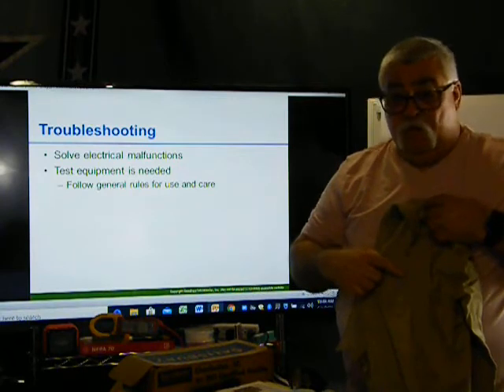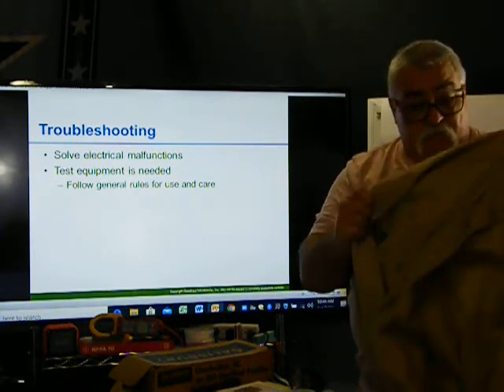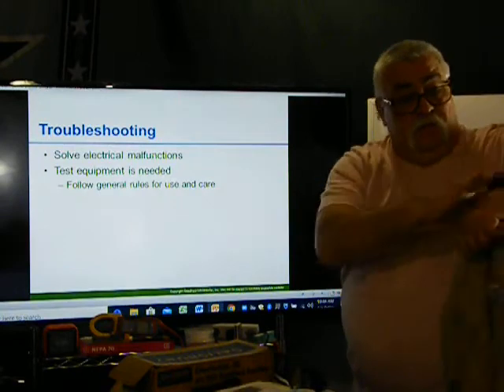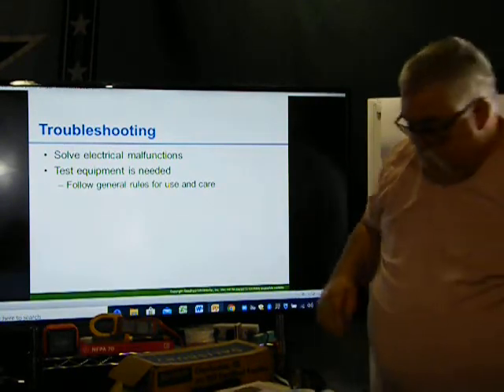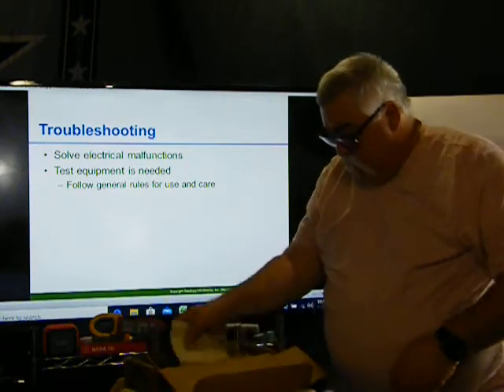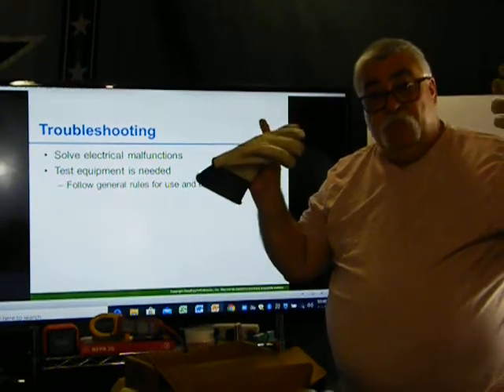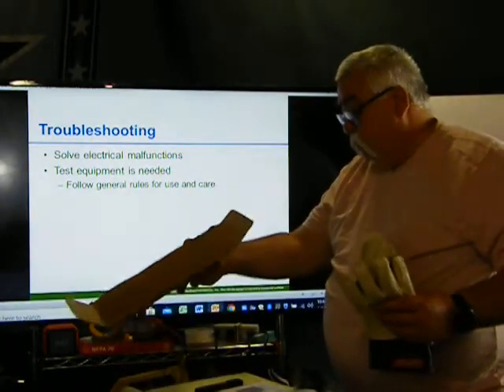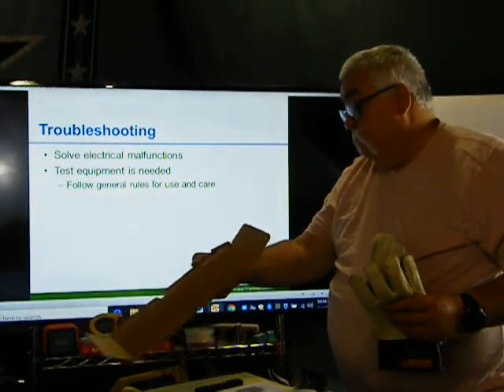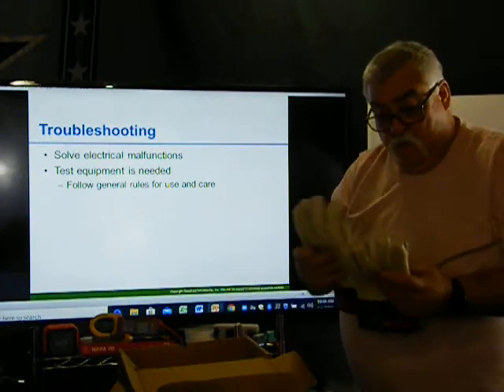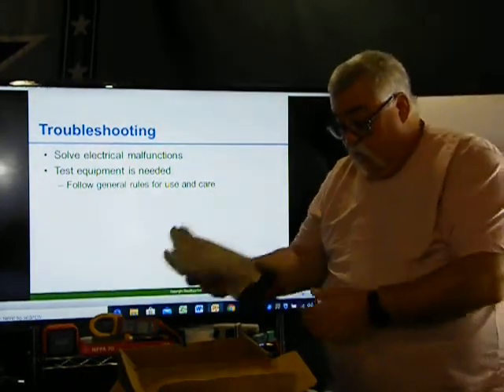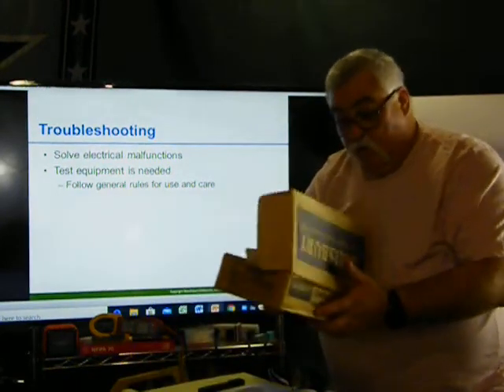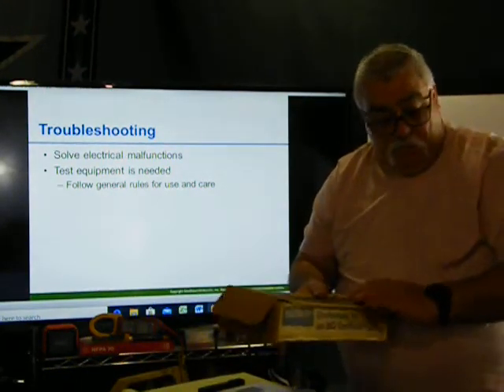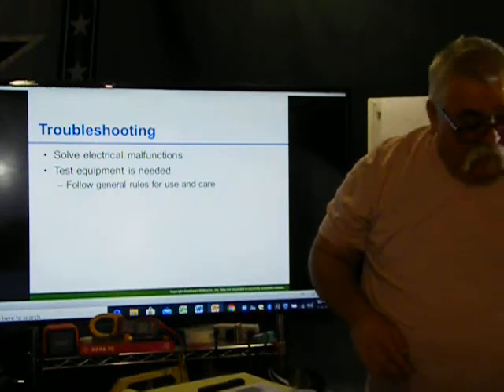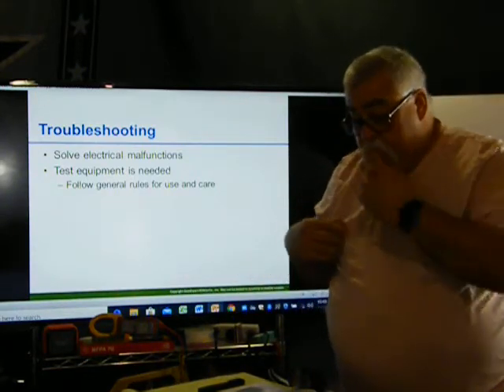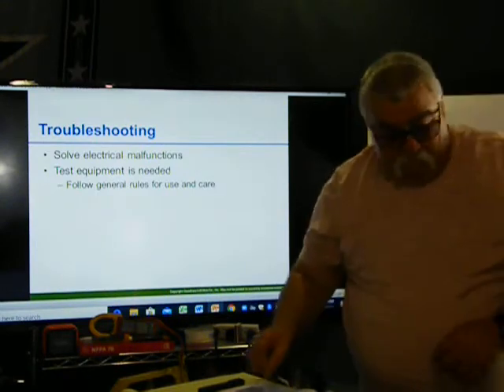Fire resistant, fire retardant, whatever you want to call it, an FR shirt, to protect you. Long sleeves protect your arms. And the other is hot gloves. These hot gloves are good up to 1,000 volts. Make sure you test them. I keep mine in a box, so that whenever I need them, they're there. My shirt, whenever I'm going to work in a panel or anything, I'll put it on. I usually keep that in a plastic bag.